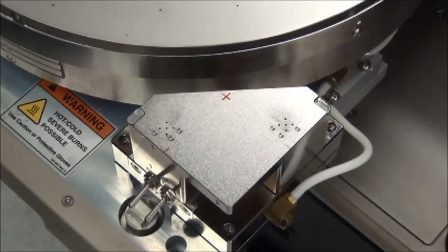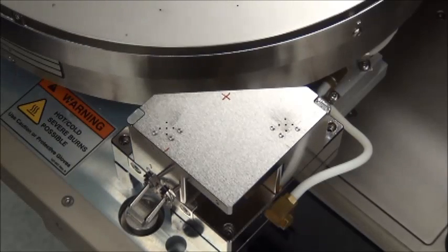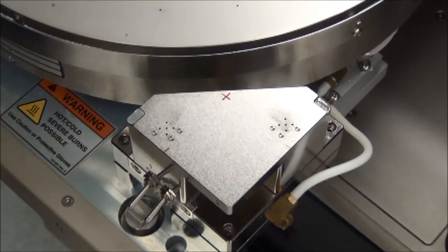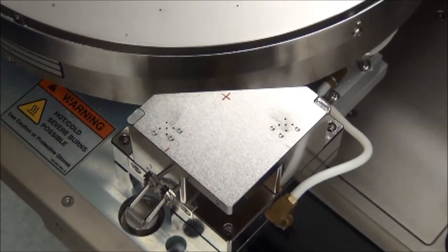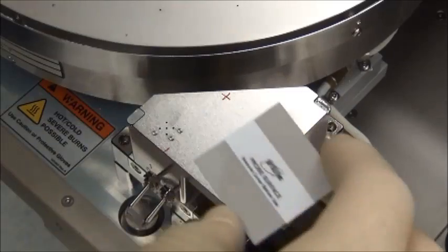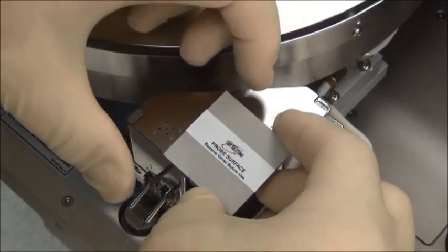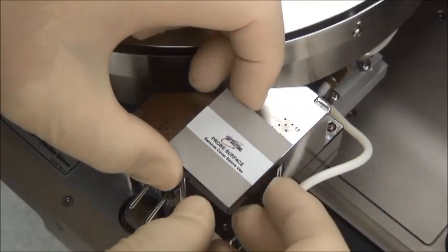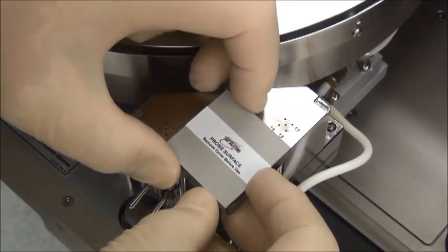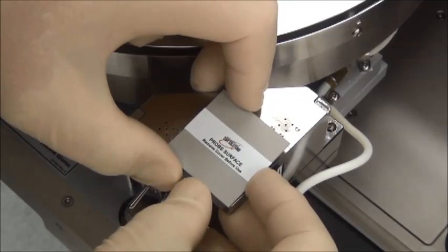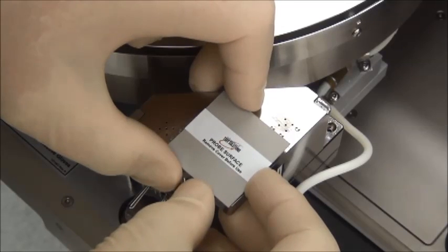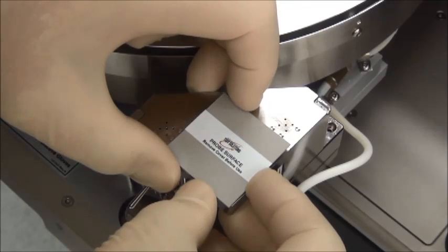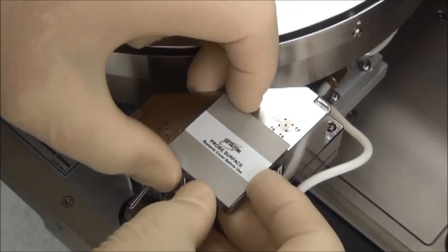We are finally ready to install the cleaning pad to the aux chuck surface. First we remove the protective cover from the adhesive side of the cleaning pad. Be careful to avoid transfer or collection of any debris on this surface when removing the cover. Next, we align the edges of the cleaning pad to the right and bottom edges of the aux chuck and then gently place the pad onto the surface of the chuck.